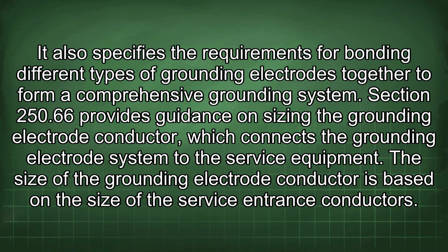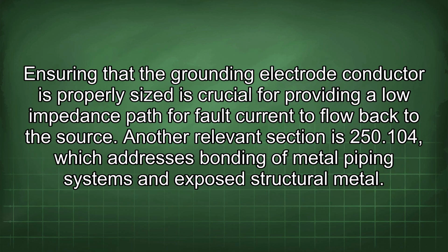It also specifies the requirements for bonding different types of grounding electrodes together to form a comprehensive grounding system. Section 250.66 provides guidance on sizing the grounding electrode conductor, which connects the grounding electrode system to the service equipment. The size of the grounding electrode conductor is based on the size of the service entrance conductors. Ensuring that the grounding electrode conductor is properly sized is crucial for providing a low impedance path for fault current to flow back to the source.